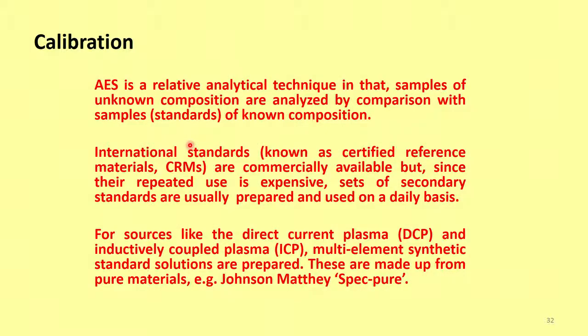So, we have to construct a calibration curve in ICP as well as spectrophotometry, atomic absorption or any other technique which is not an absolute technique. So, the secondary standards are normally prepared on a daily basis. For sources like DCP, direct current plasma, and ICP, we can also go for multi-element synthetic standard solutions.